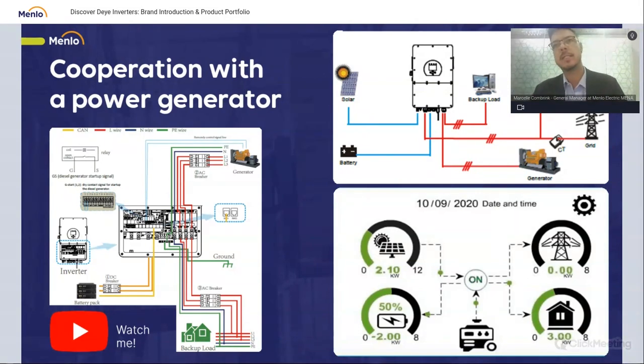What I need to emphasize here is that the generator must have an automatic start-stop, because it needs to receive a signal from the Deye system to start and to stop the generator. And it needs to be a three-phase generator, so three-phase with three-phase inverter. You can't take a three-phase inverter and put a single-phase generator on it. It needs to be three-phase with three-phase.